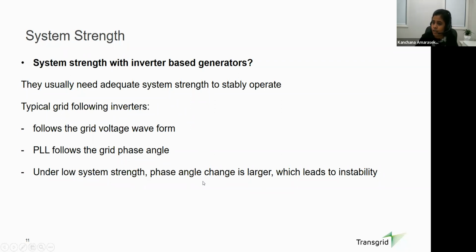So this is one key reason why conventional or widely used grid-following inverters can lead to instabilities in systems with low system strength. Usually, for stable operation, these grid-following inverters need adequate system strength. When we talk about system strength, we usually refer to a concept called short circuit ratio, or SCR, which is defined as the ratio between the fault level and the plant MVA capacity. Usually grid-following inverters can operate down to an SCR of 3 without any issue, but when system conditions go below an SCR of 3, under very low system strength conditions, they struggle to operate stably.